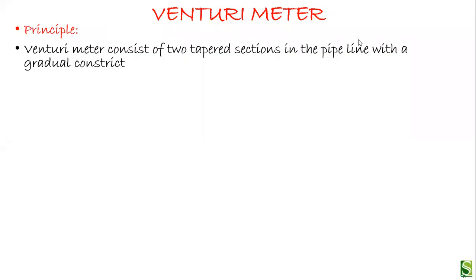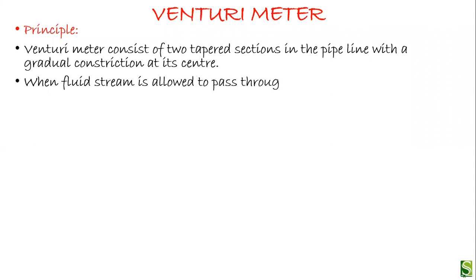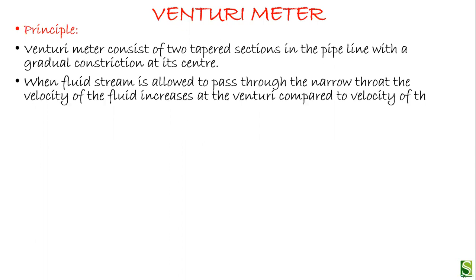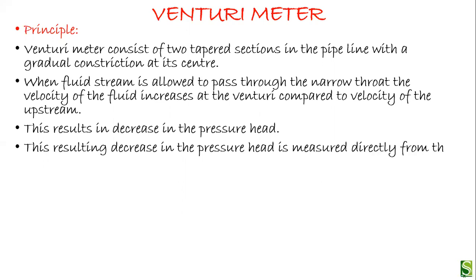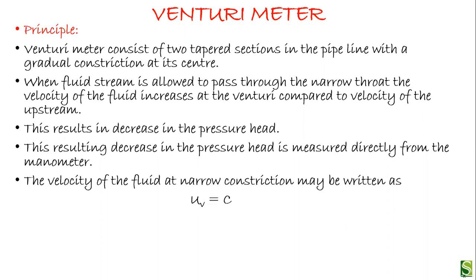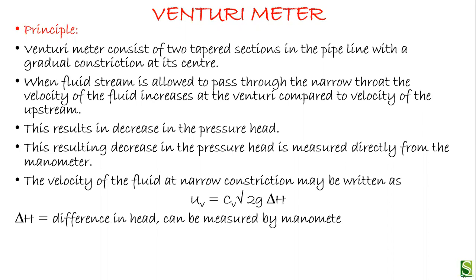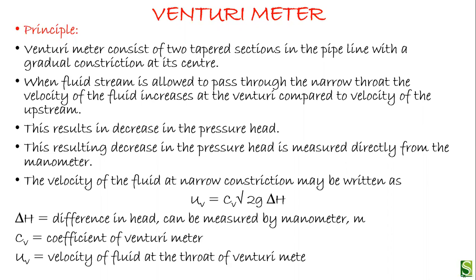Next we look at the venturi meter. Its principle: it consists of two tapered sections in the pipeline with a gradual constriction at its center — the throat. When the fluid stream passes through the narrow throat, the velocity increases compared to upstream, resulting in a decrease in pressure head. This decrease can be measured using a manometer. The velocity at the narrow constriction is: uᵥ = Cᵥ√(2g·Δh), where Δh is the difference in height, Cᵥ is the coefficient of the venturi meter, and μᵥ is the velocity at the throat.